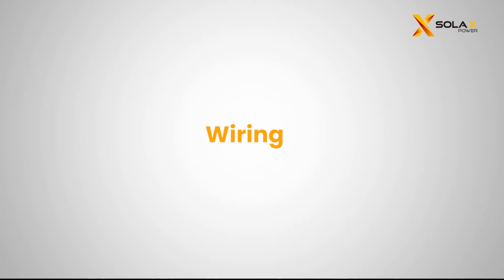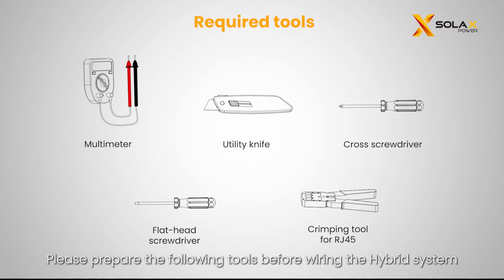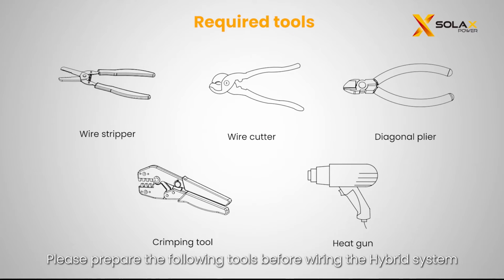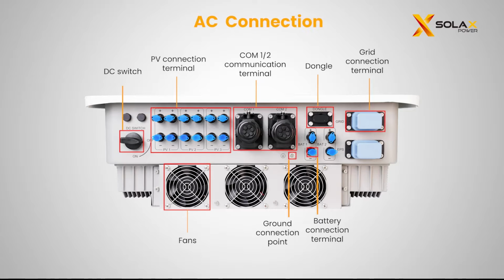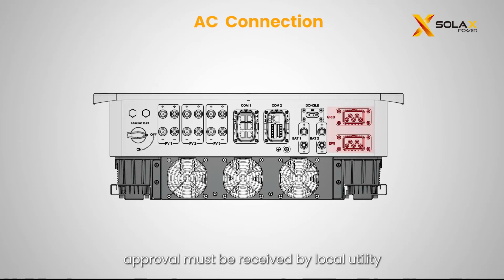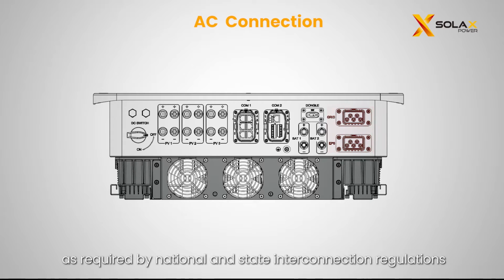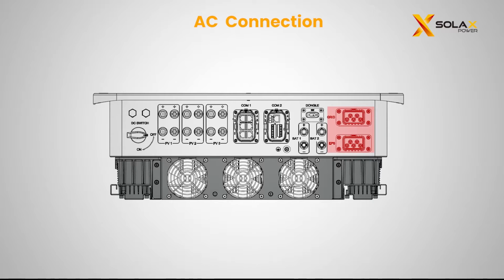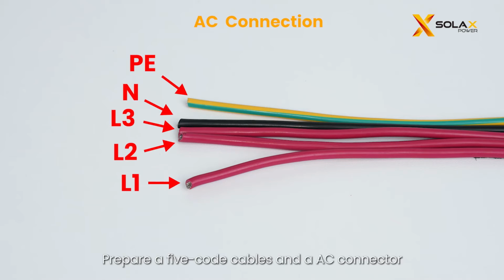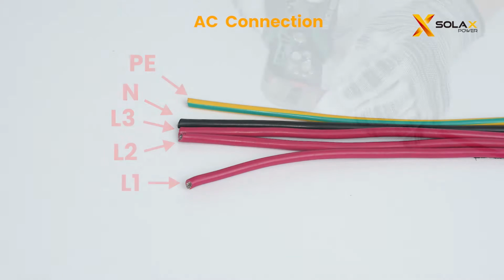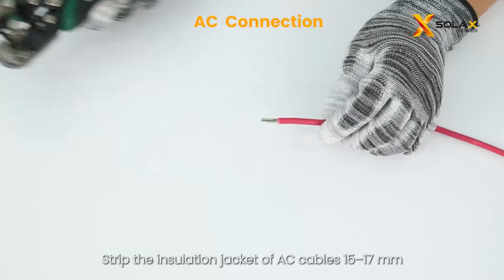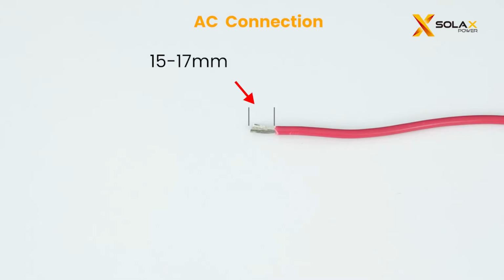Next, we'll move on to the wiring session. Please prepare the following tools before wiring the hybrid system. Before connecting the inverter to the grid, approval must be received by local utility as required by national and state interconnection regulations. Prepare a 5-core cable and an AC connector. Strip the insulation jacket of AC cables 15 to 17 millimeters.